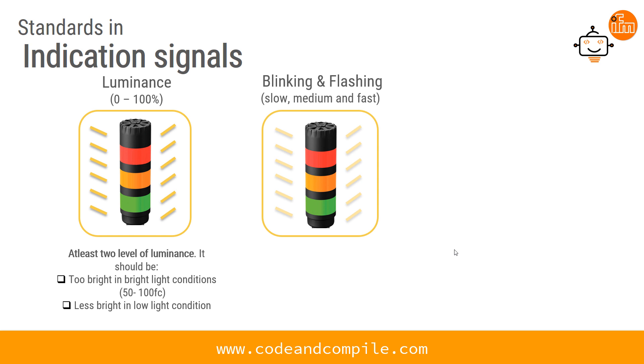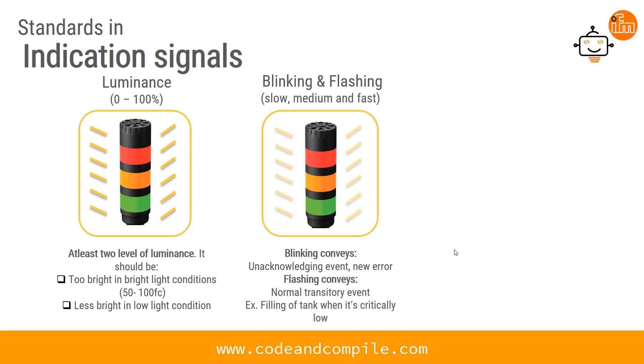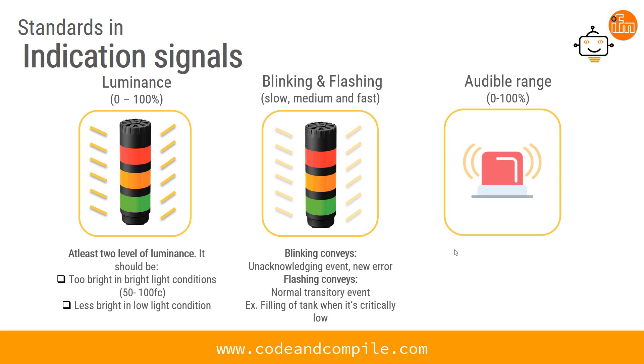The second standard is about blinking and flashing. The blinking and flashing rates should allow the user to differentiate different sequences — slow, medium, and fast. Generally, blinking is used for unacknowledged events or new errors, while flashing is used for normal transitory events such as the filling of a tank.